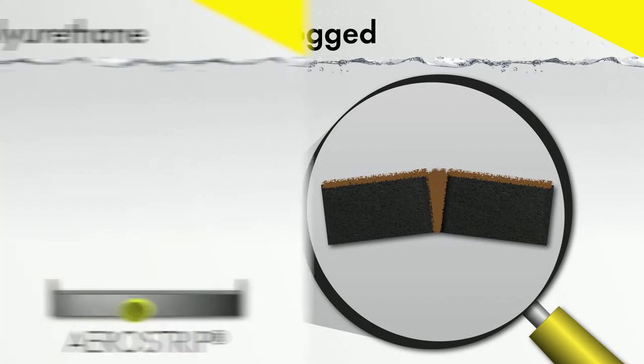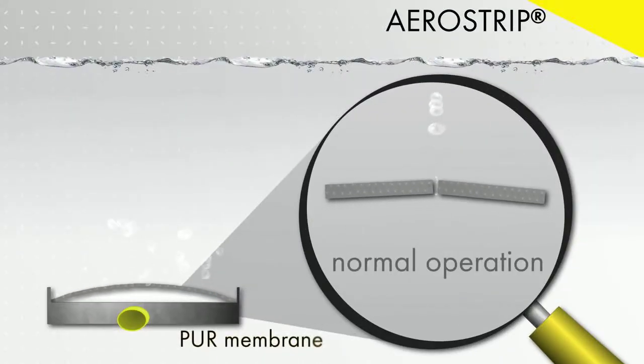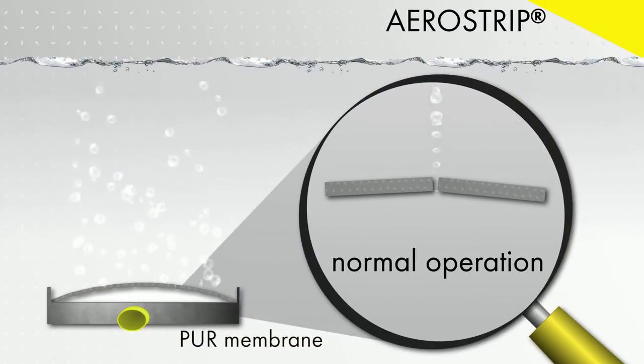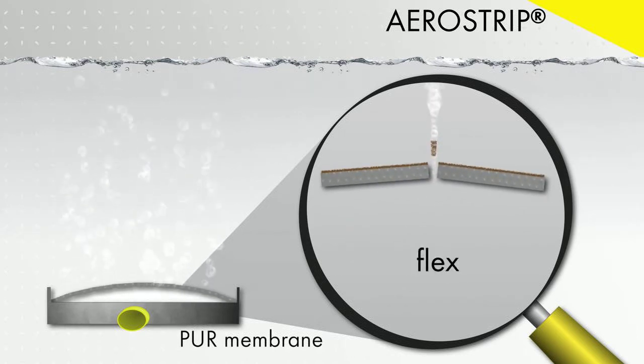The Aerostrip diffuser uses a polyurethane membrane that is much thinner than typical membrane materials, which means there is less surface area in the perforation for biofilm to grow on. Additionally, the polyurethane membrane remains elastic over the lifetime of the diffuser, which makes a relaxed seal possible.